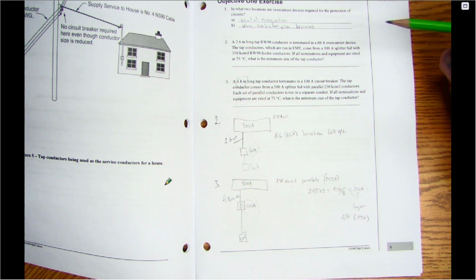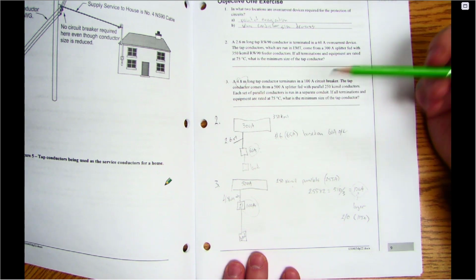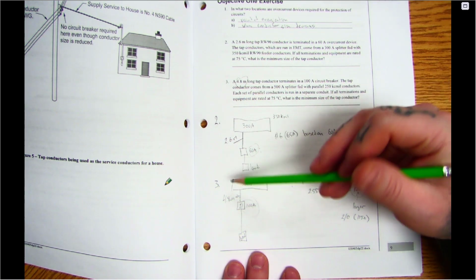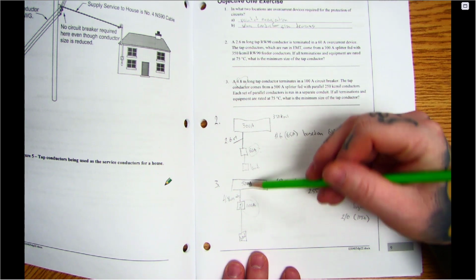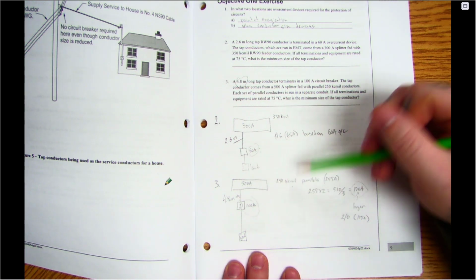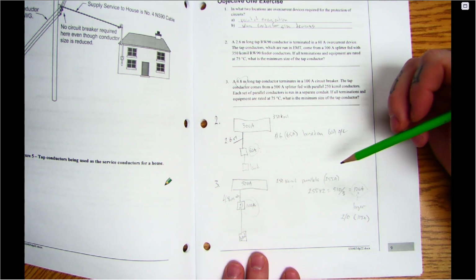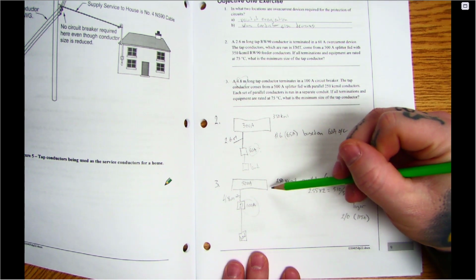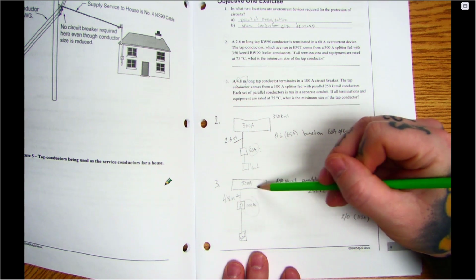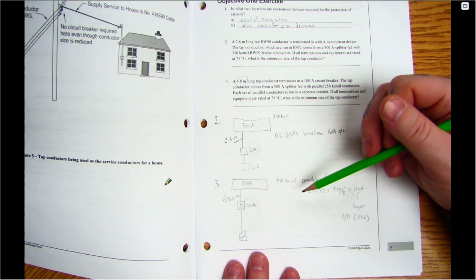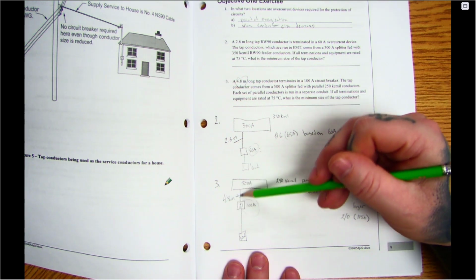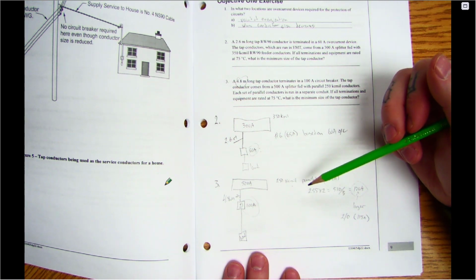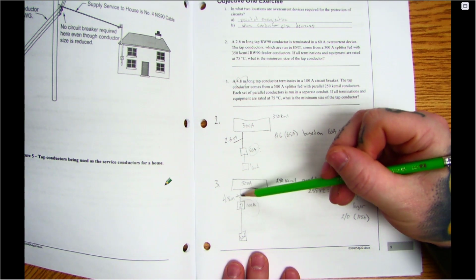So that's still an advantage. You might have seen in your experience a splitter with a bunch of disconnects right above it, like in a service room or control room. You'll see all these disconnects really close to the splitter where they're getting their supply from. The reason they do that is to take advantage of these rules.